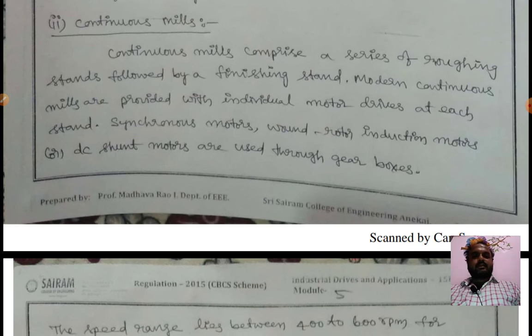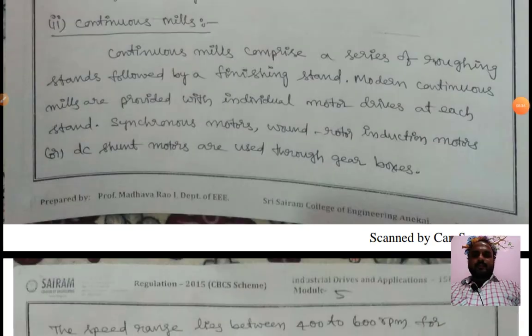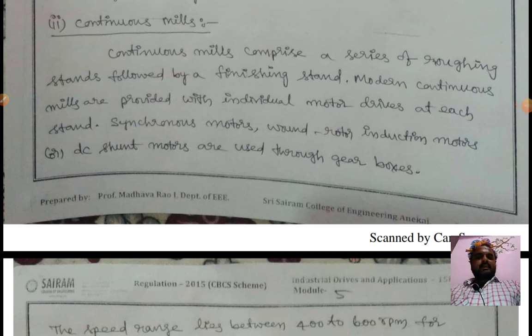Continuous mills comprise a series of roughing stands followed by finishing stands. Modern continuous mills are provided with individual motor drives at each stand. Synchronous motors, wound rotor motors, or DC motors are used.